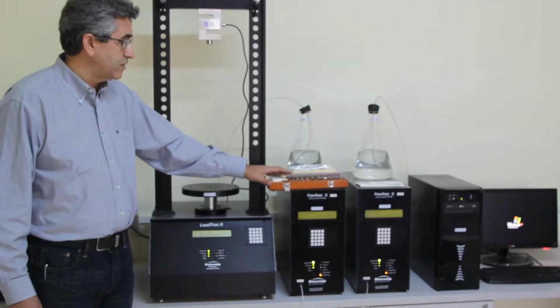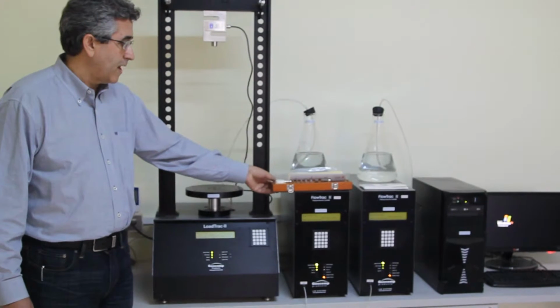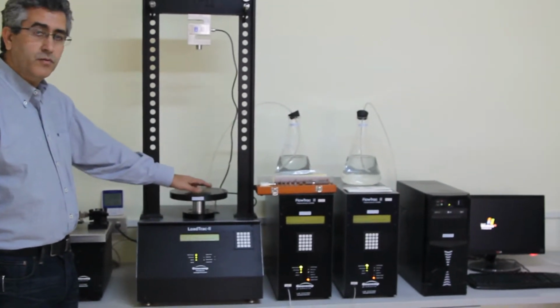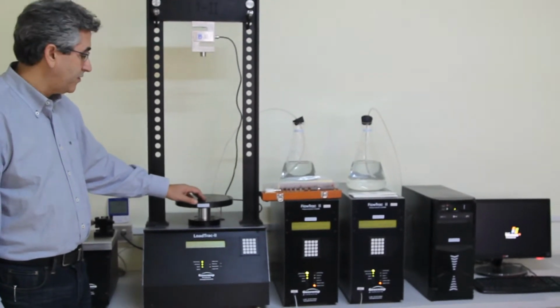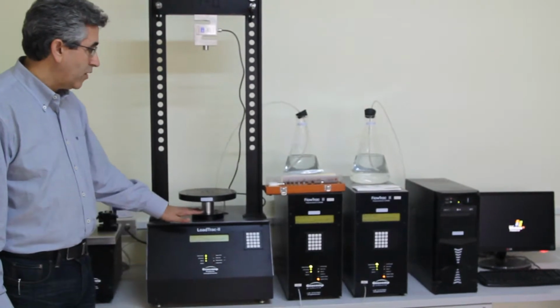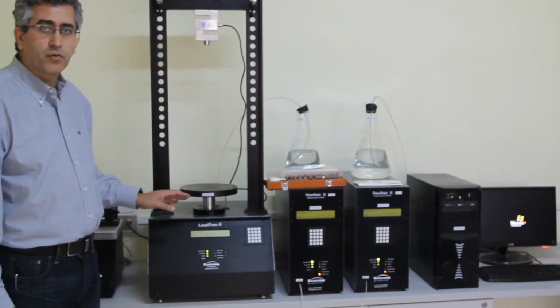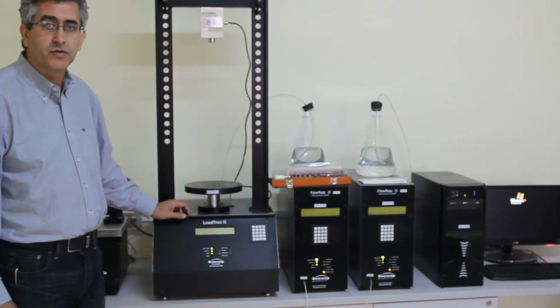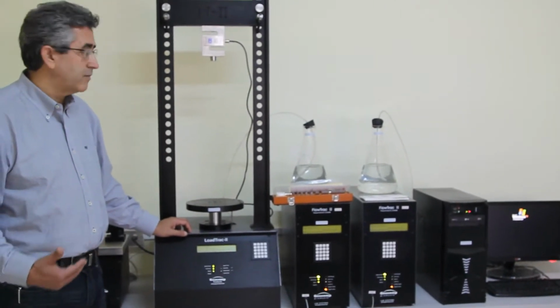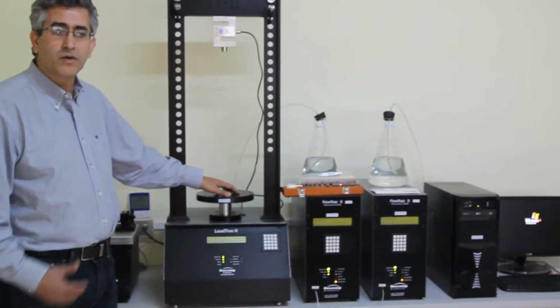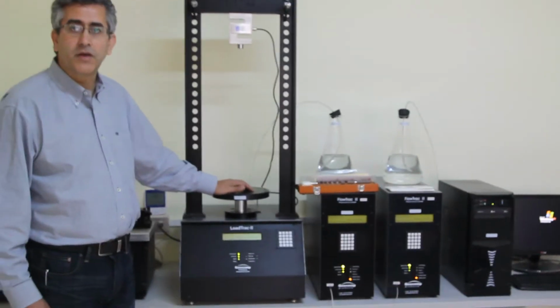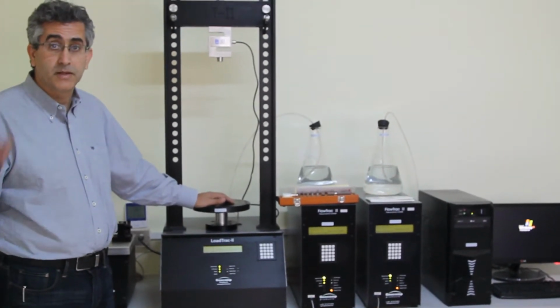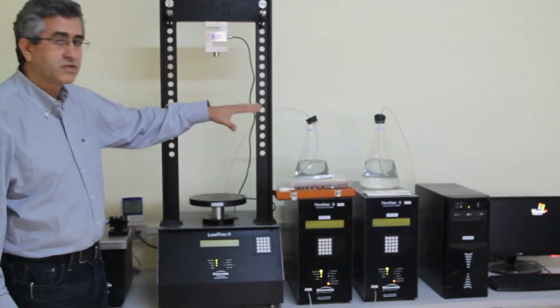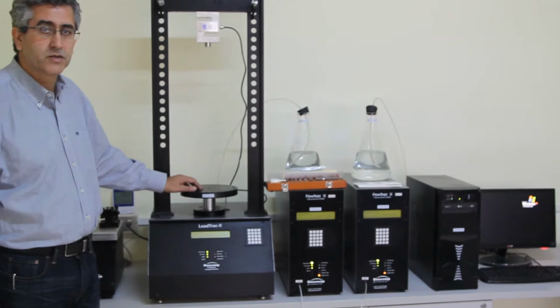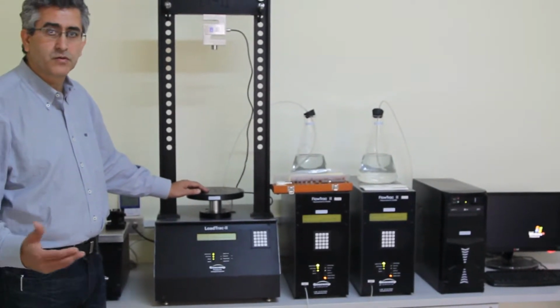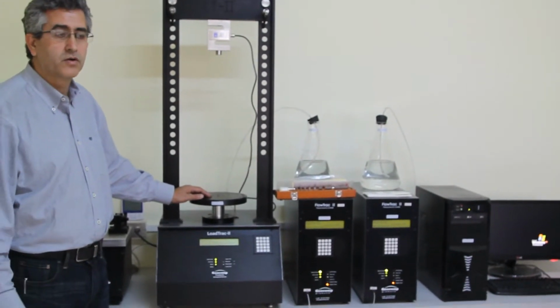Okay, we have our calibration devices, which are the gauge blocks. They are ready. Also, we have moved our platen to about halfway, which corresponded to about 850K in terms of microsteps. Now what we are going to do is use a software program that has built-in menus to do our calibration. You can use any software program that uses a displacement sensor to do your calibration, and once you do the calibration once using the software, then all you have to do is cut and paste it into a different software if you have multiple software programs. In this case, because it's a triaxial system, we are going to be using the triaxial software. Alternatively, you could be using a consolidation software or an unconfined compression software or the CBR software.